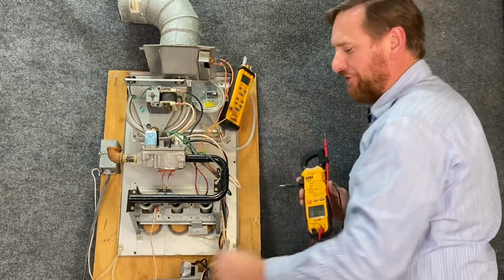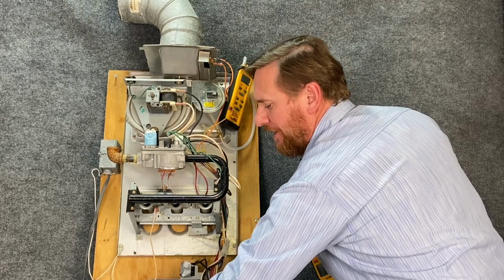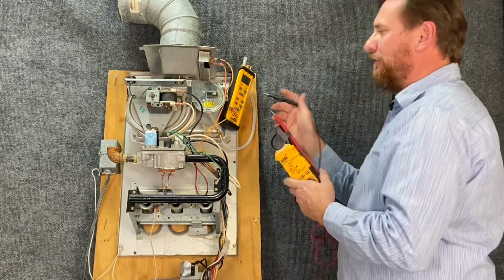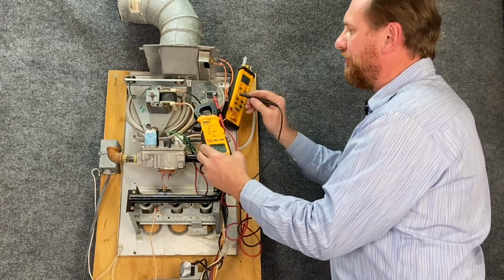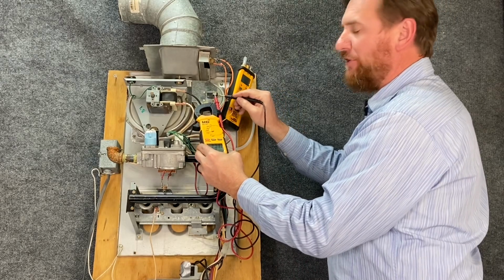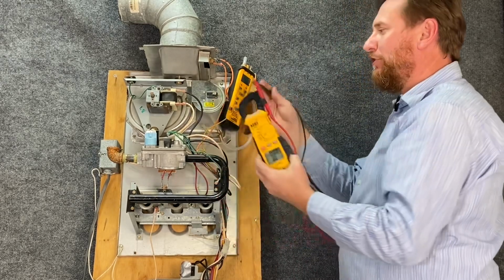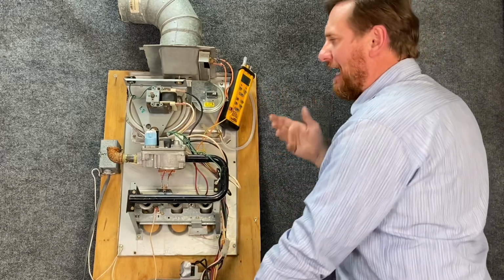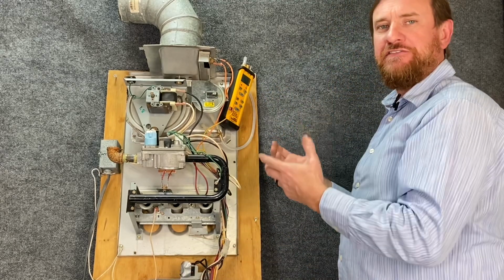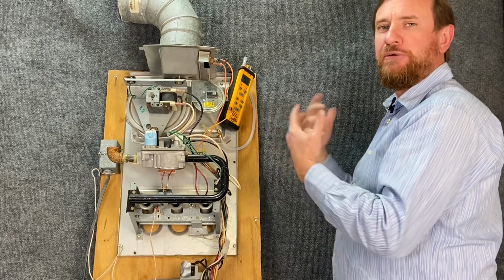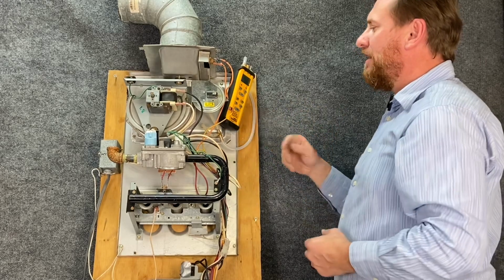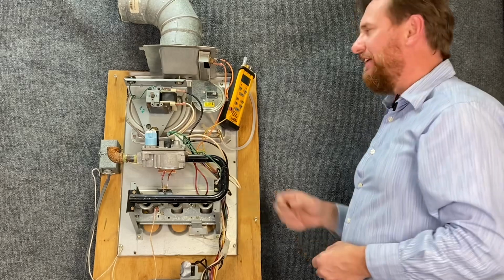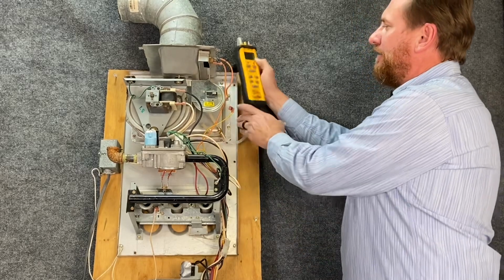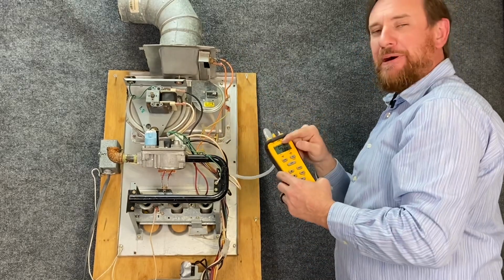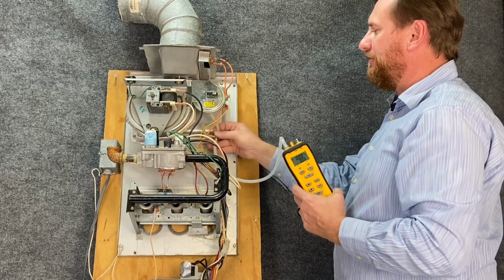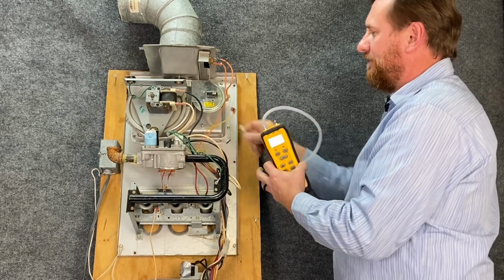My switch is closed. If I shut my fan motor off, I lose my vacuum, and the switch will open. So if we check the resistance now, we show OL, the switch is open. Two different ways of checking the switch. I prefer the voltage method because it's faster. I don't have to pull wires loose or worry about wire connections going bad. There is a third way of checking this. This particular model of manometer has a pump built into it. So we're going to set that up next.